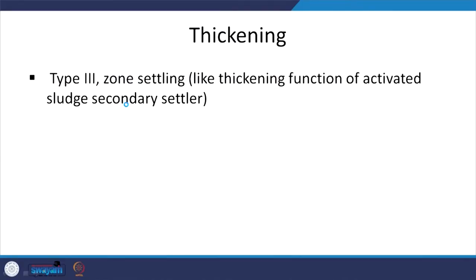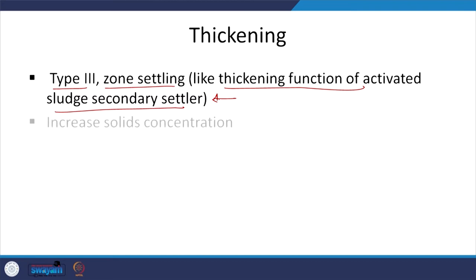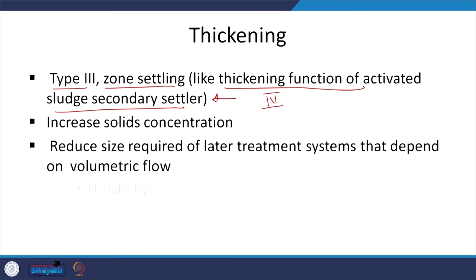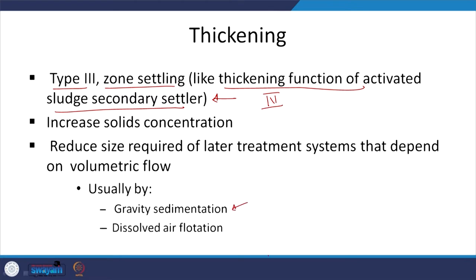Type 3 is zone settling, where you have a clear interface between relatively clear water with lower solid concentration at the top and solids at high concentration below. Much further down you see compression settling — Type 4. This is like the thickening function of the activated sludge secondary settler, which we discussed in that context. Most widely used is gravity sedimentation. Sometimes dissolved air flotation is used depending upon the type of sludge.